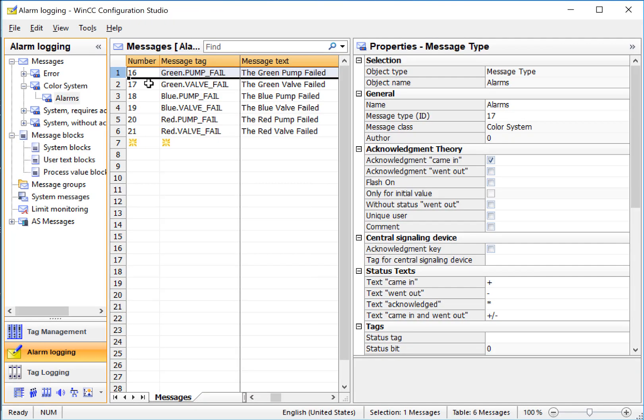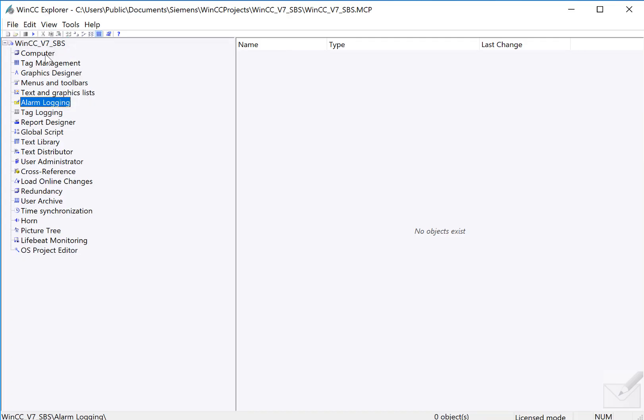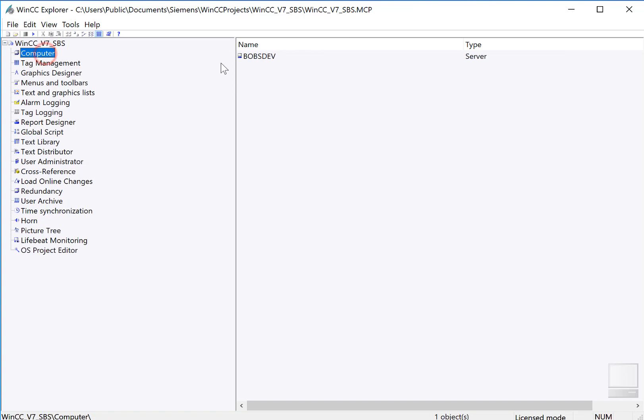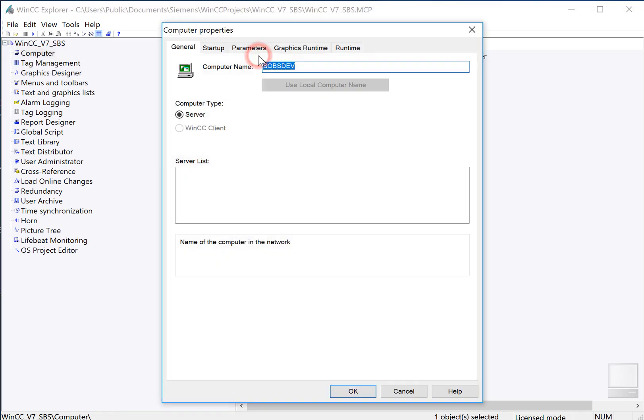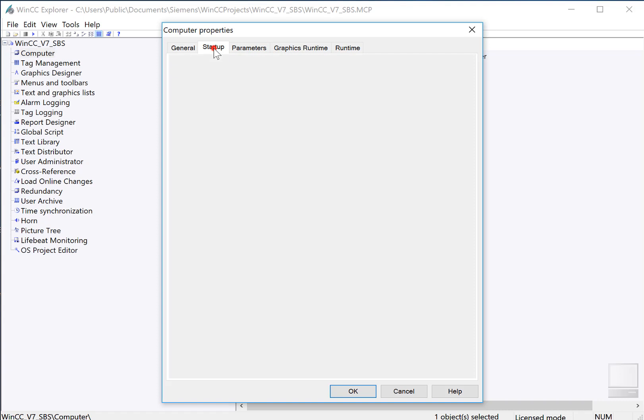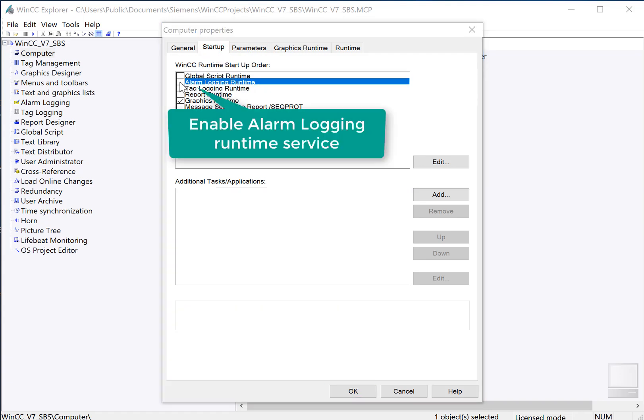So that's it for now in Alarm Logging Editor. The next step is to go back to WinCC Explorer. Make sure you are not in runtime. Go to Computer and your Project Server. And then we'll go to the Startup tab. Here is where we turn on the alarm system. So we just check it and click OK.